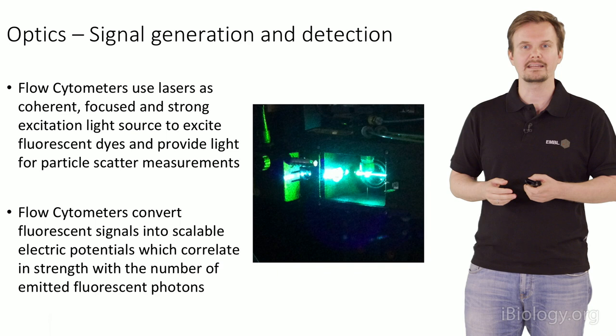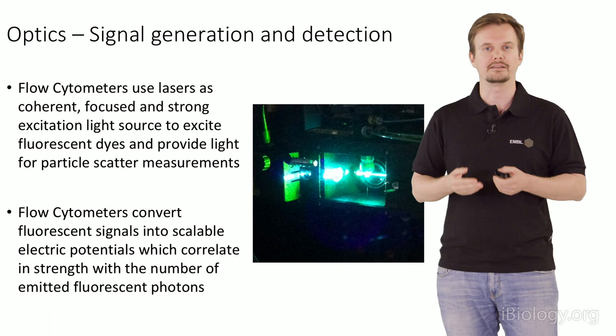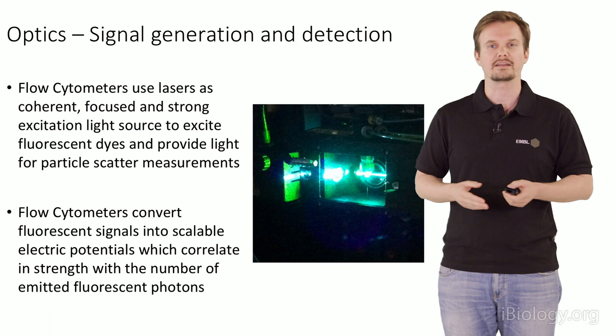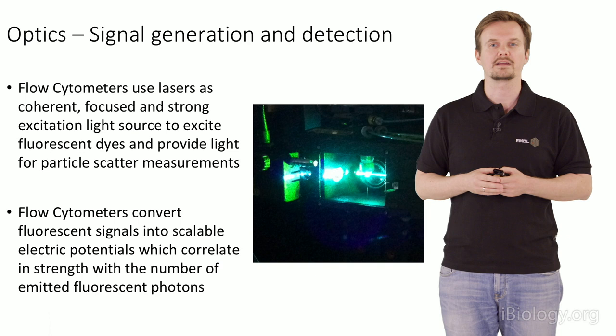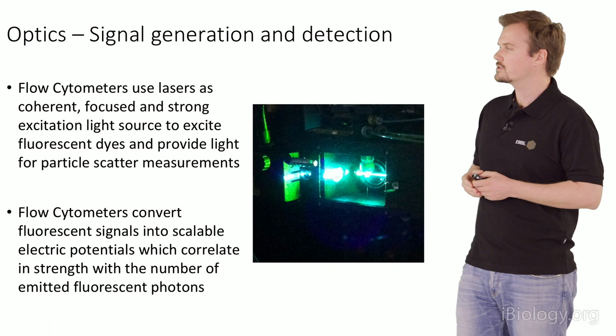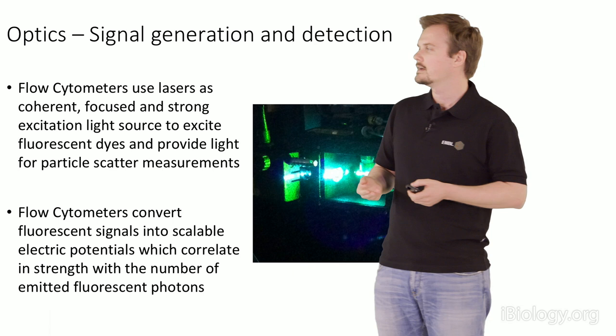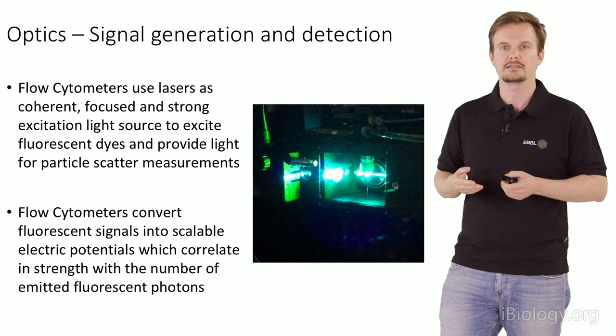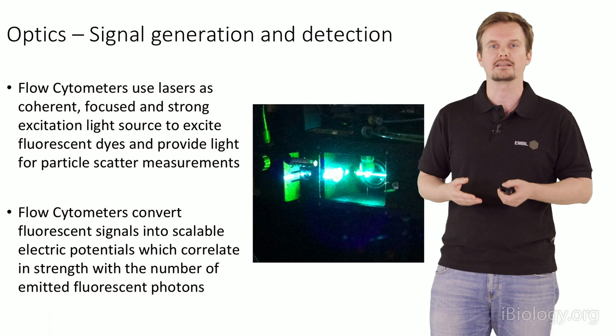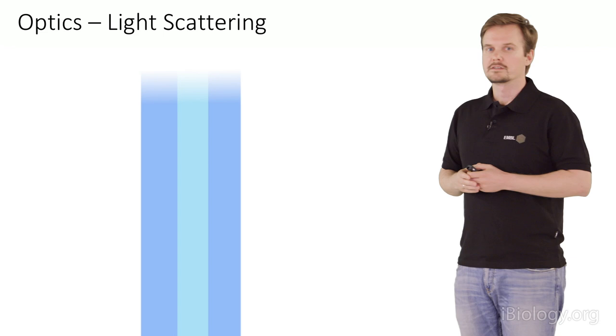Flow cytometry is dependent on excitation. Anything we can excite to generate fluorescence in a cellular format can be analyzed. We can put in strong lasers of different wavelengths to create a variety of excitation potentials to fit any question, if we have a dye that reports it via fluorescence. In conventional flow cytometers, we use lasers because they're coherent, focused, and easy to integrate. Ultimately, a flow cytometer converts the number of fluorescent photons emitted in our system into a discrete electrical value.